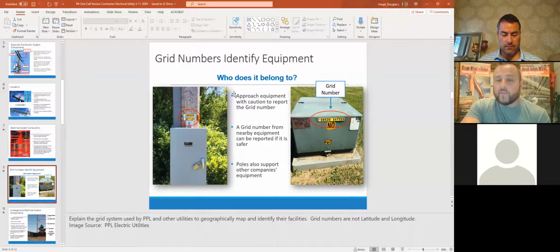And more so, if you can give us that grid number close to your site, we can actually put that into our computer in our truck, and it's going to show us the grid itself. We may be able to go to an operating device and actually de-energize the line before we even get to you. Because we're able to pull up the grid, go to a sectionalizing device and say, you know what, they dug into a three-phase underground line, we're going to get this section de-energized and remotely change some things around. So the grid number, if it's possible, when you're calling in, is very helpful.